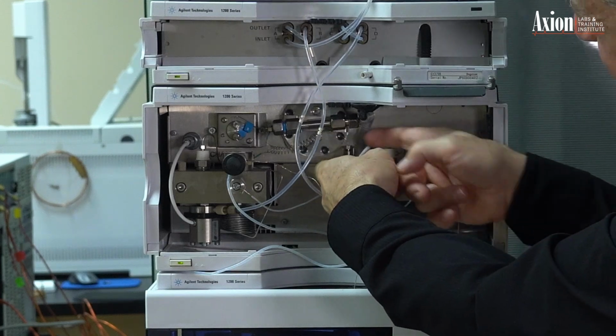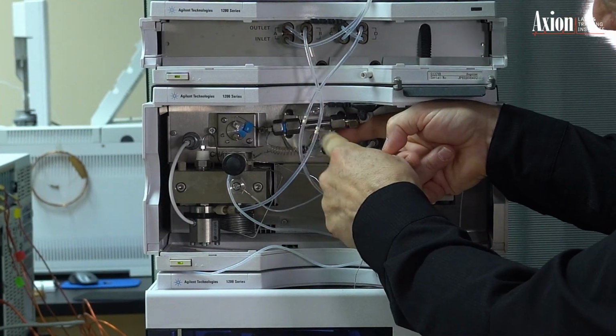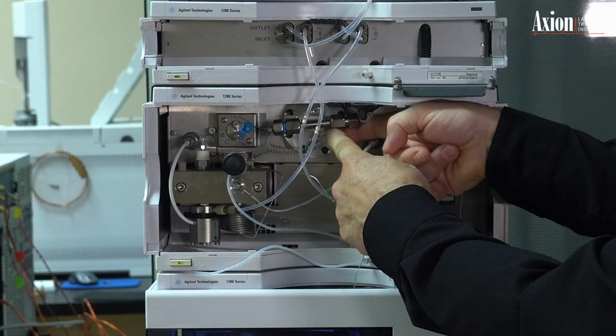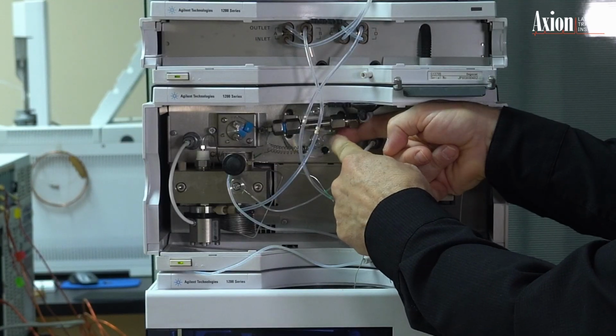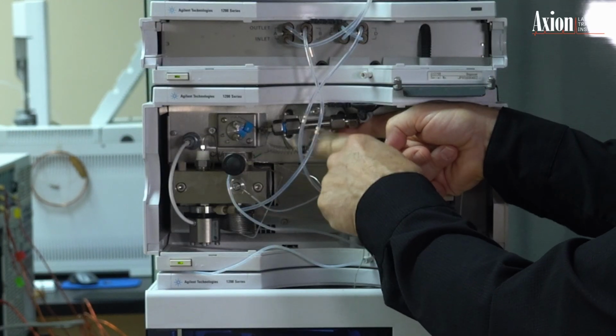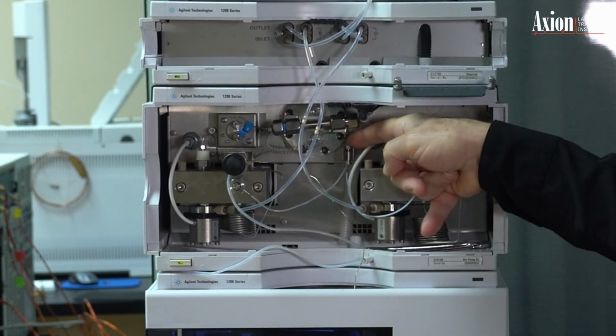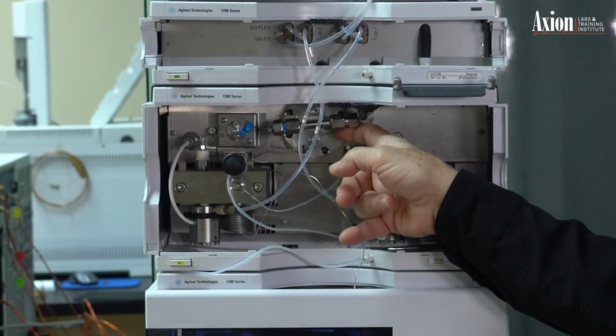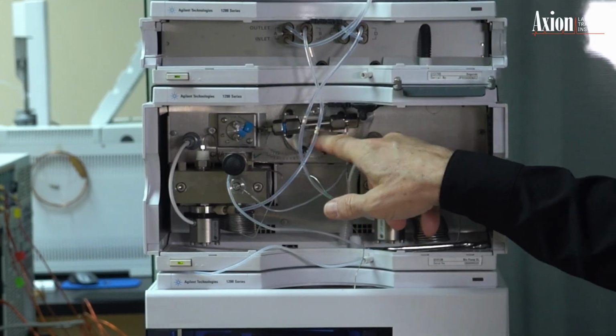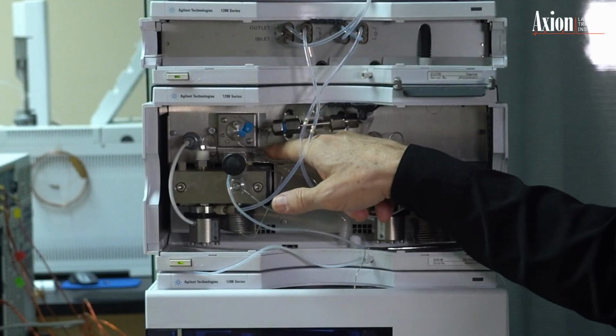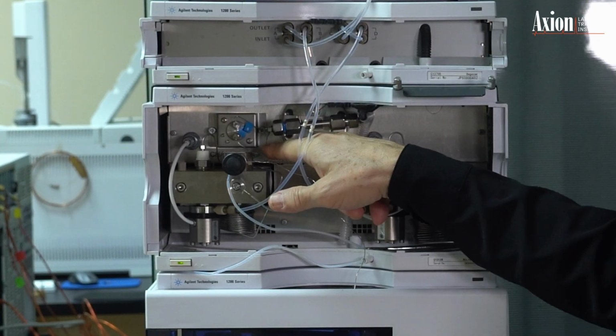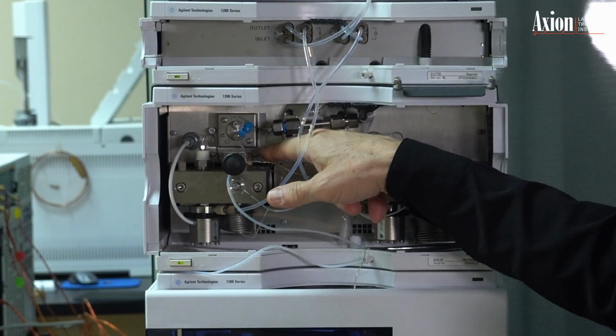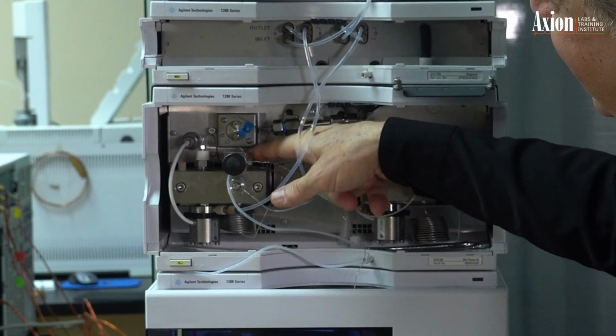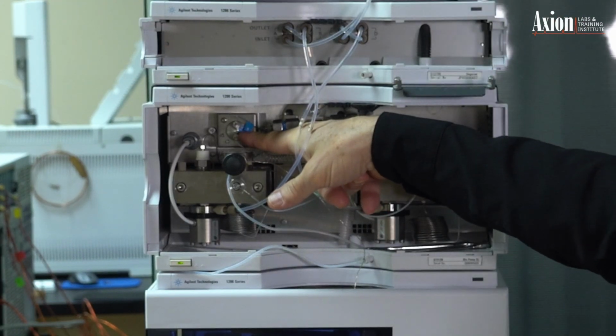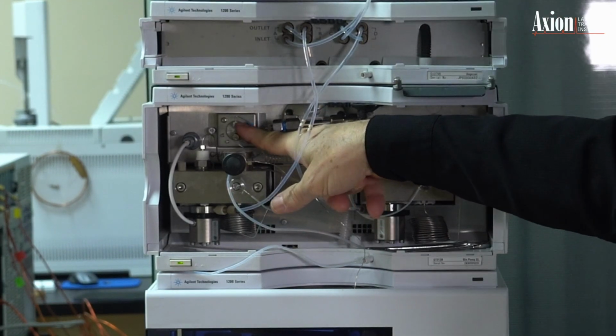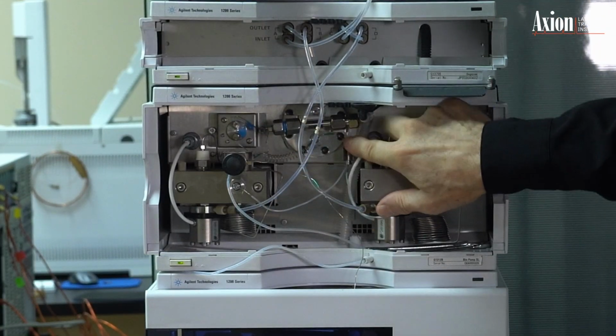So this one that comes out, it's a little hard to see, this is really small capillary tubing. You see a little green piece of tape on it. So it's this coil, and this is the output. At this point, we could then take it to the autosampler to get our sample, but the folks at Axion are very nitpicky about the way the pulsations work, so they're going to remove even the tiny little pulsation that's there. We're going to remove it. So we go into a pressure transducer, let's measure the pressure, and then out of the pressure transducer, we go into the pulse dampener.